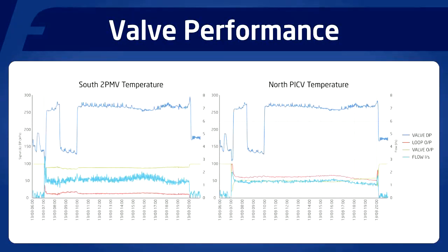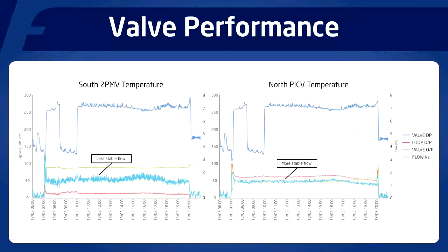We can see that the stem position of the pressure independent control valve is far more in the central range, and is shown here on this graph as a percentage against the left hand y-axis. The flow is both more stable in the pressure independent control valve and has far fewer oscillations when compared with the flow through the conventional two-port modulating valve.